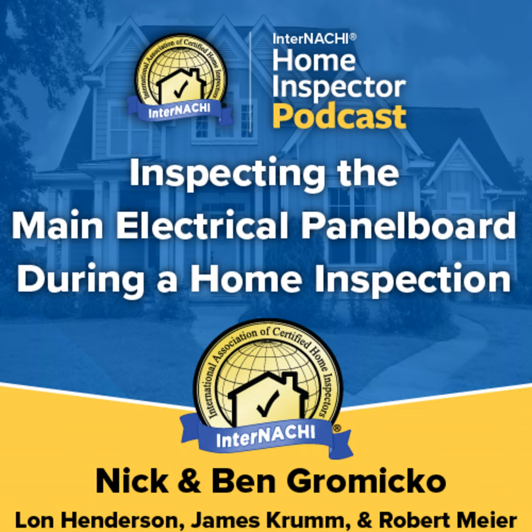Until 2002, the NEC simply stated that panel boards must be installed according to Underwriters Laboratory, or UL 67. UL 67 states, quote, "An individual terminal shall be provided for the connection of each branch circuit neutral conductor," unquote. The NEC has never allowed double-lugging neutrals, even if it did not specifically address the topic until 2002.